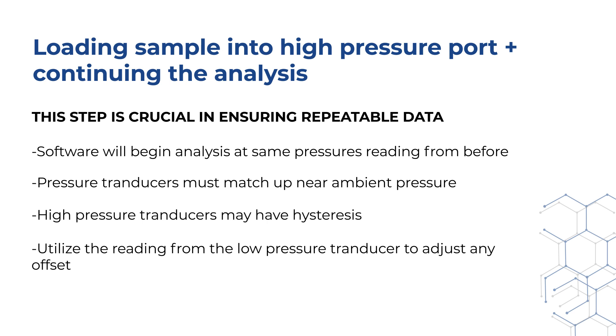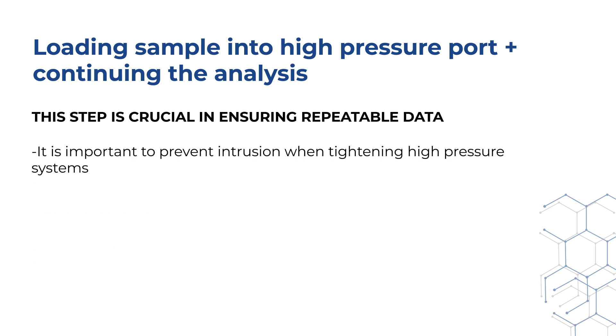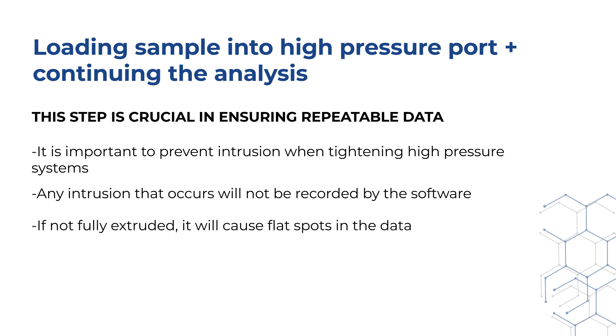It is important as well that we do not cause any intrusion to take place while tightening the high-pressure system. Any intrusion that occurs while tightening will not be recorded by the software, and if it does not fully extrude once tightening is complete, will leave a flat spot in the cumulative intrusion at the crossover point between the low and high-pressure portions of the analysis.